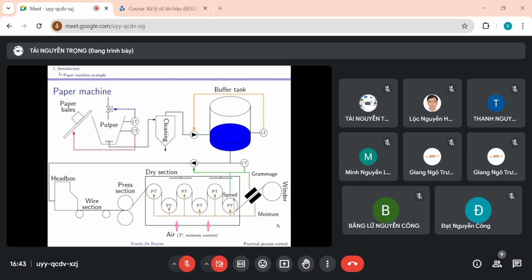Well, we arrive now at the next control loop, shown in orange over here, and this is the level control in this tank. The level is controlled using this pump. This level controller will be quite different to the level controller that we have seen over here. There, the level has to be maintained on set point in a very strict way. What we'll see at the output of this tank is that when a machine starts, there is a sudden step-like demand of flow. So the output will look like this. Now imagine that we have a controller implemented here that is of the type implemented over here, so a controller that will maintain the level in the tank very strictly.